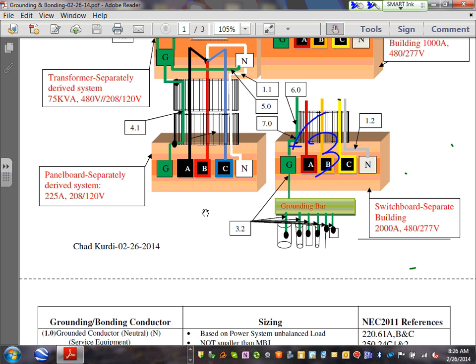So this is number 3. So Adam, if you have a project and you have a second building, the first thing you want to ask yourself and ask your project manager: I need to establish a grounding electrode system here. What does that mean? I need a copper bar right in the electrical room, and I need to take a wire to the plate, a wire to the ground ring, a wire to the steel, a wire to the water, a wire to the foundation concrete encased electrodes. All these are called electrodes. You know, steel of a building, foundation of the building, ground ring, ground rod, water, what else, Adam? A tank. If you have a big tank underground, a metallic tank, you can tie to it. You cannot tie to the gas line. Gas line is unacceptable underground.